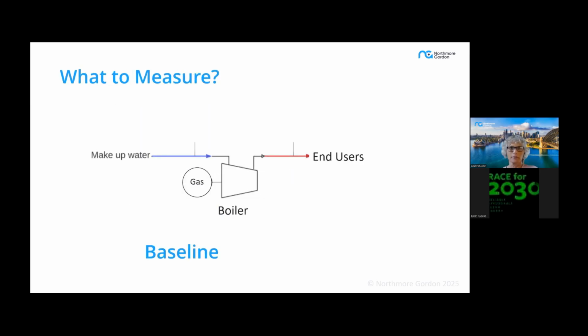So in terms of what to measure, starting with a baseline, you need to understand what your system looks like beforehand to inform your project design, and then for comparison of before and after. Now, submetering of the gas at the boiler is sometimes used for certificate creation M&V, but not always. But it's very important for being able to provide the appropriate design of your heat pump system. Now, a gas meter on the boiler is important for your project design if your site has other users of natural gas that are more than a small part of the site gas consumption, because otherwise you're not going to truly understand what the gas consumption of the boiler is.